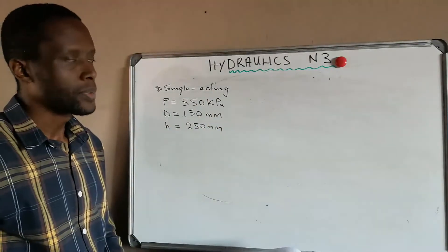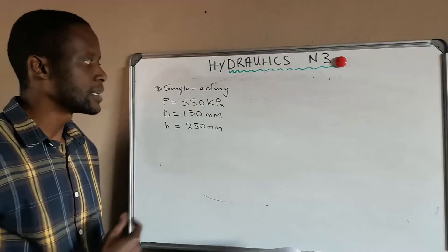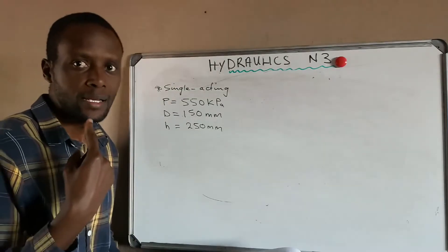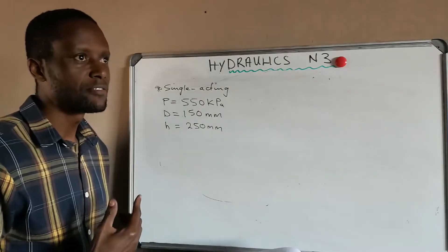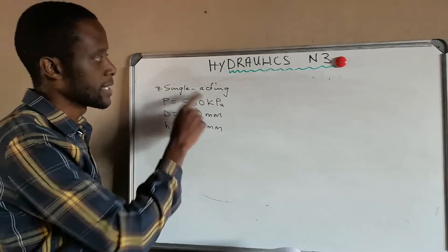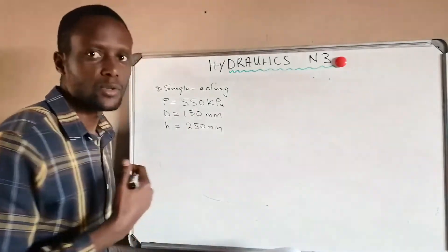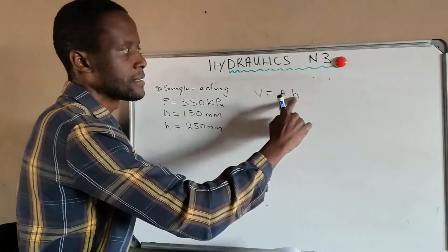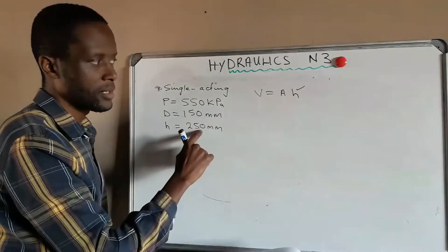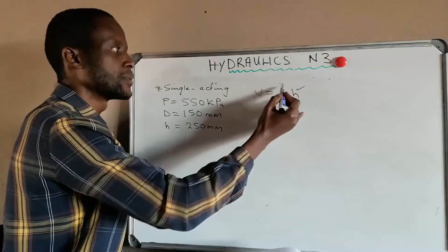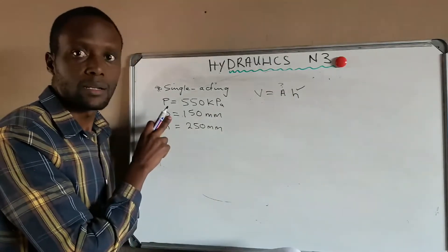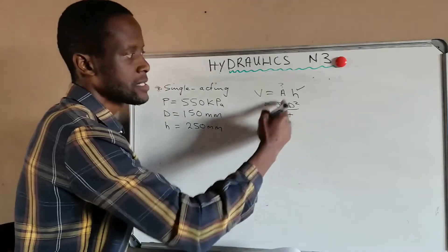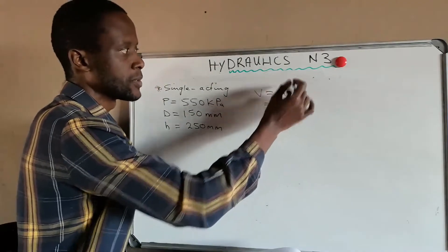Keep in mind this is a single acting pump. If it were a double acting pump, we would multiply the volume by two because a double acting pump delivers twice in one stroke. For a single acting pump it only delivers once per stroke. For the volume per stroke: volume equals the area of the piston times the stroke length. We have stroke length 250mm, but we need the area from the diameter.